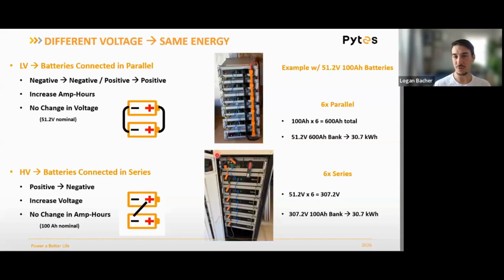Commercial or high voltage systems are the opposite: we're connecting those battery modules in series. There's a lot of benefits in using high voltage batteries for commercial applications, but it's not like we're magically creating energy out of thin air. If you have the same amount of batteries at the end of the day, six modules, your energy totals are identical. All that we're changing is our voltage and our amp hours.